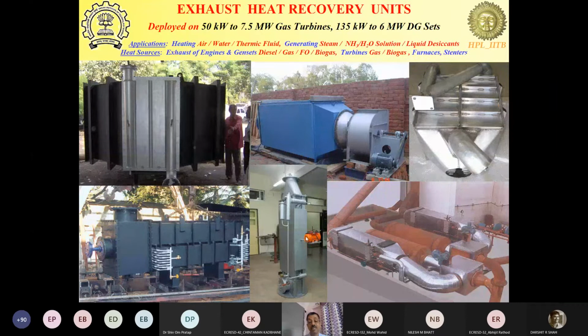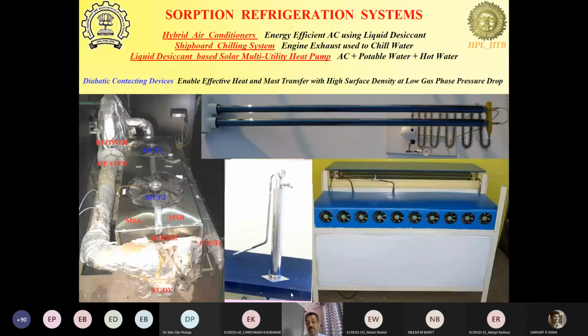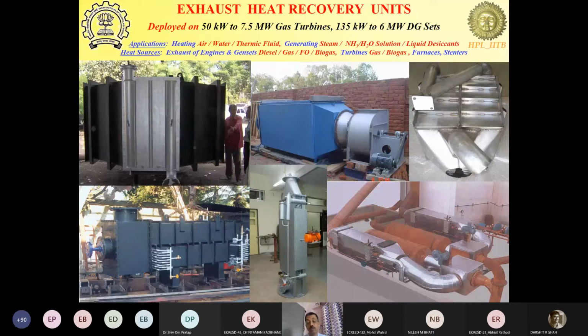And in this particular case, the exhaust gases had a lot of dry, fluffy soot, unburned carbon. So we developed a heat exchanger whose surface can be vibrated, and the entire dust would get collected down below. Earlier, with a conventional shell and tube heat exchanger, they had to open it up almost every day to clean the tubes where soot would get deposited. After we installed this, we automated the cleaning cycle as 20 seconds every 4 hours.